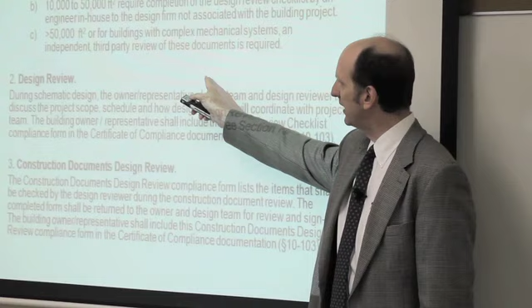This one here is going to surprise a lot of engineers: design phase review. If I'm doing a job that's less than 10,000 square feet, my little firm can sign off on it on my own. If it's 10,000 to 50,000 square feet, I've got to get somebody else in my firm to sign off on my lighting control design, to make sure it meets all the California requirements. If it's 50,000 square feet or greater, your design firm has to go to an outside design firm to do a lighting control and lighting design review to make sure you're meeting the California requirements.